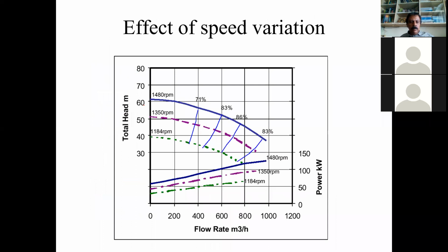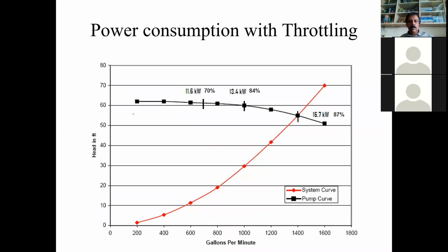The other option is to go in for a speed change. If you want a varying requirement, as we already discussed, this is 1480 RPM, 1350 RPM, and 1184 RPM. So the pump behaves like a smaller pump at reduced speeds. Depending on the requirement, you can change the speed and make it suitable for the required needs. What is the impact of a VFD? In many pump applications, we will find that the VFD is a very useful gadget with which we can control the pump speed and optimize a lot of energy.